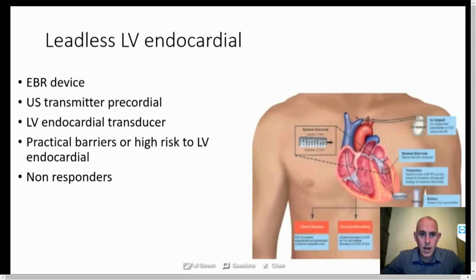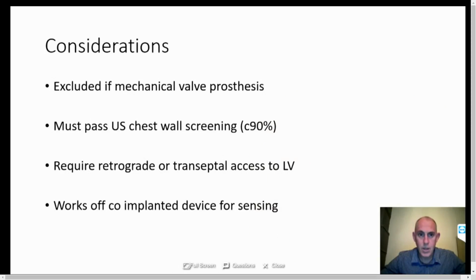There are practical barriers. This is implanted where there are practical barriers, or there's a high risk to an LV endocardial lead, or in patients who are non-responders to conventional CRT. Unfortunately, this can't be implanted if a patient has a mechanical valve prosthesis, because the acoustic noise from the mechanical valve interferes with the ultrasound signal from the transmitter to the transducer.